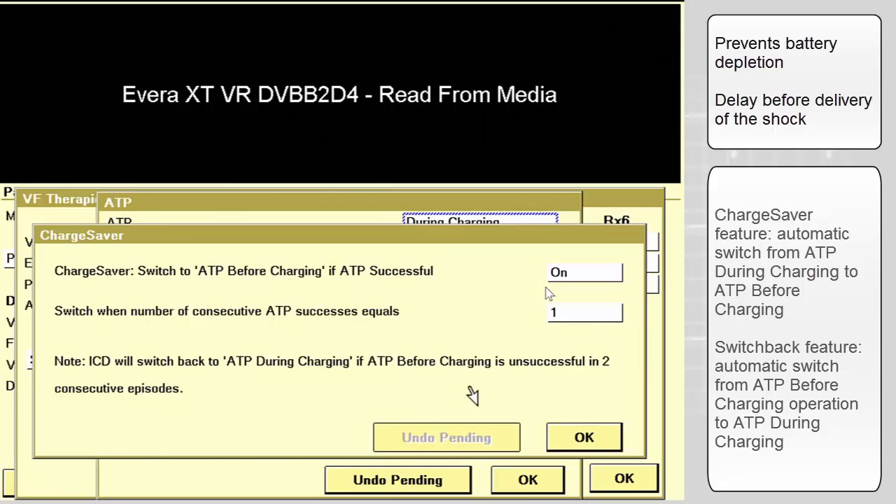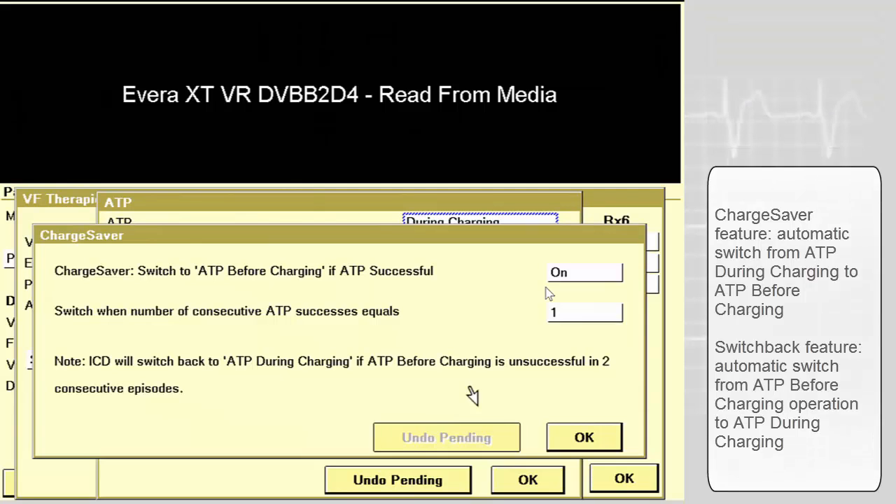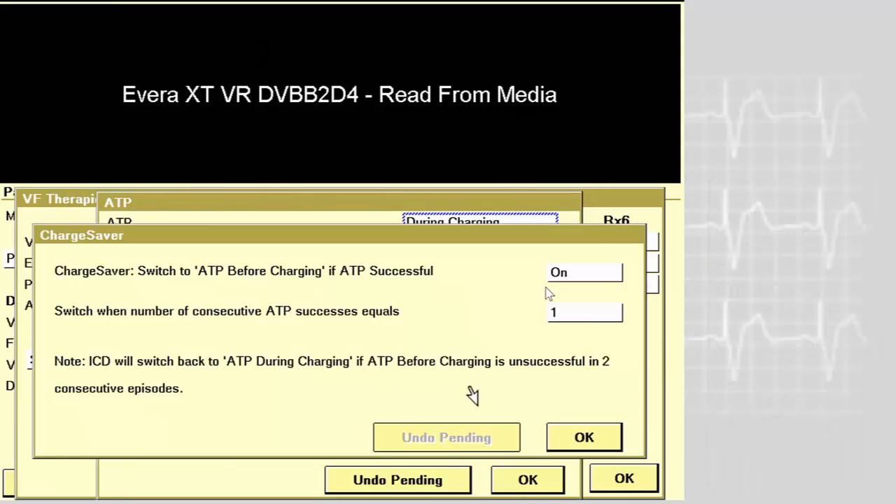If you enable the ChargeSaver option, the device can automatically switch from ATP during charging to ATP before charging. This change will occur when ATP has successfully terminated the detected arrhythmia on a programmable number of consecutive attempts — here it is programmed to one.